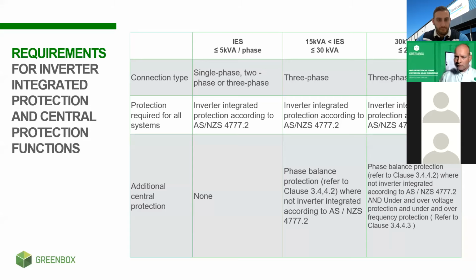Now let's look at installing it. If you're installing around 5 kilowatts, you don't need it, just install as per normal. Anything between 15 to 30 kilowatts, you do need phase balancing, but the network protection device still isn't required. Then from 30 kilowatts up to about 100 kilowatts, that's where you're required to install the network protection device.